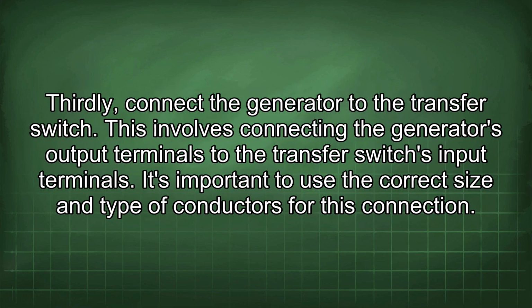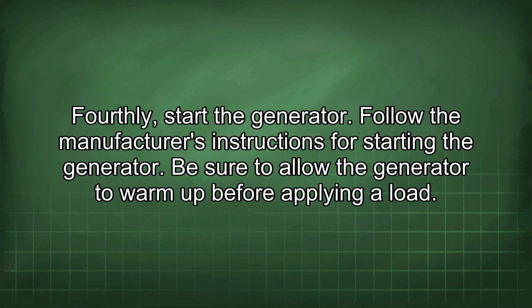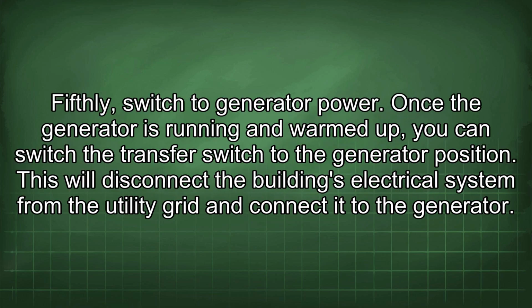Thirdly, connect the generator to the transfer switch. This involves connecting the generator's output terminals to the transfer switch's input terminals. It's important to use the correct size and type of conductors for this connection. Fourthly, start the generator. Follow the manufacturer's instructions for starting the generator. Be sure to allow the generator to warm up before applying a load. Fifthly, switch to generator power. Once the generator is running and warmed up, you can switch the transfer switch to the generator position. This will disconnect the building's electrical system from the utility grid and connect it to the generator.